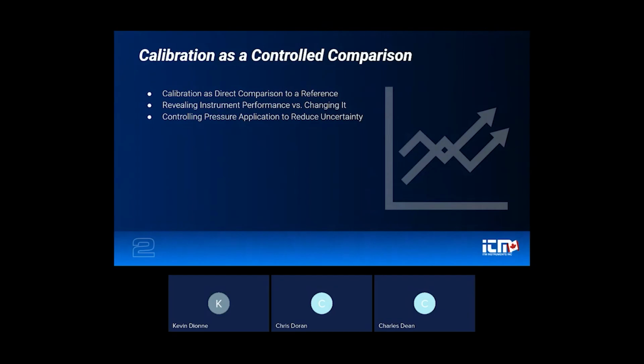The effectiveness of calibration depends heavily on how pressure is applied and controlled during the test. Inconsistent pressure generation, unstable hold points, or poor resolution can introduce uncertainty that has nothing to do with the instrument being tested. That's why calibration should be viewed as a controlled measurement process, not a procedural process. The goal is repeatability and comparability of results, not simply passing or failing an instrument.